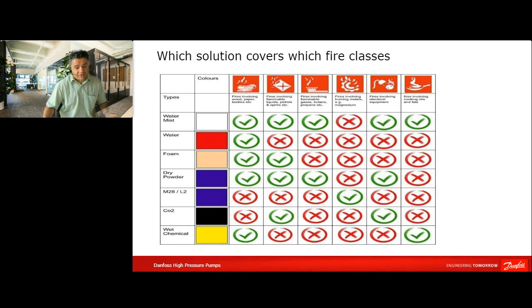For sure, there are also limitations, like you can see with burning metals. We don't recommend using water mist or water for those burning metals. But if you look at the remaining fire types, you can see that the application of high pressure water mist is the best solution compared to the others. When you convert that to a data center building, it means that you can combine many different areas, many different risks with one unique system. But we come to that later.